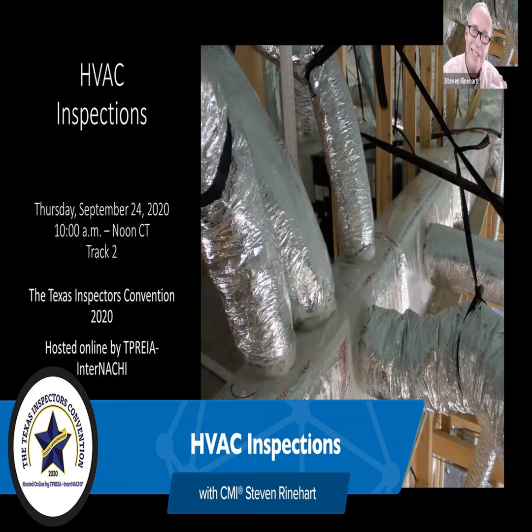I want to see it all the way up, and I want to see flashing. I don't want to see it touching the roof deck as it goes out through the roof. And when I'm up on the roof, I want to see it sticking up on the roof, high enough and secure. So you're kind of looking at all of those things right there.